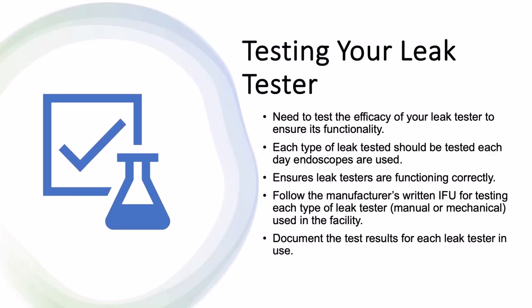Testing your leak tester. You need to test if your leak tester is working properly. Who knew? Each type of leak tester should be tested each day the endoscopes are used. Make sure your leak testers are functioning correctly. Follow the manufacturer's instructions for testing each type of leak tester, whether it be manual or mechanical, that's used in your facility, and document the test results for each leak tester in use. So you're going to have 2 records, one on testing your leak tester and one on the actual leak test results.